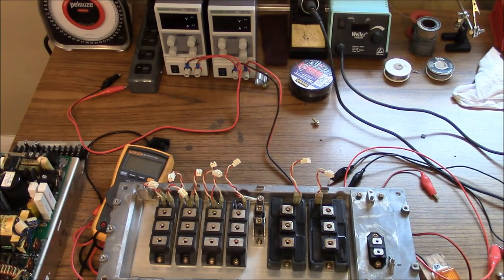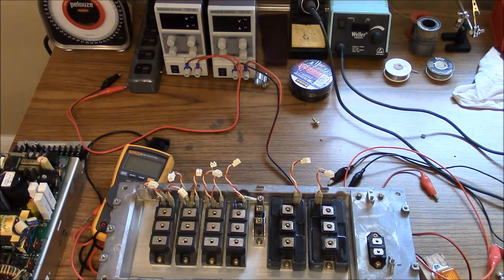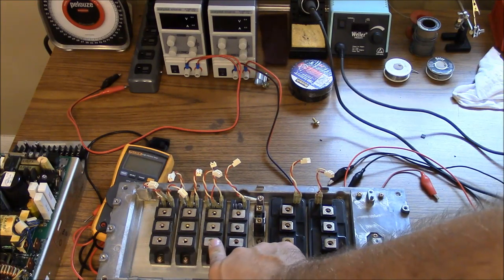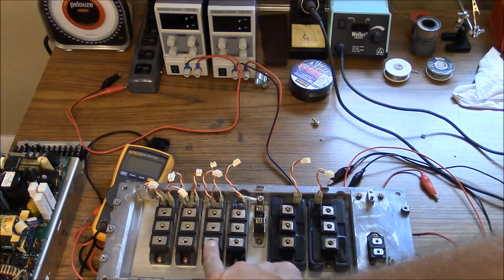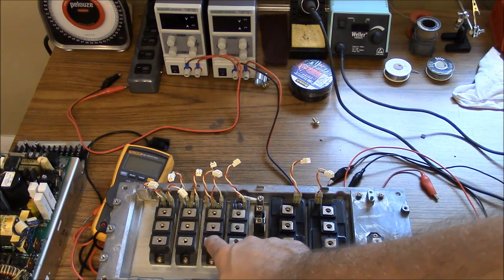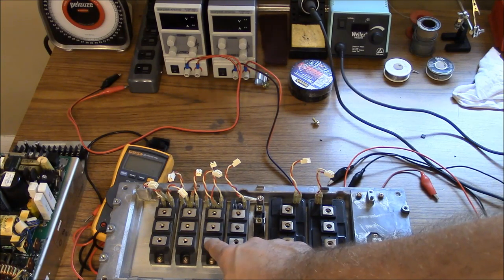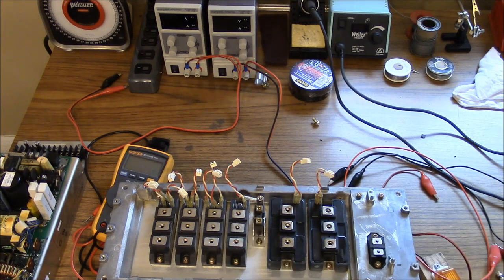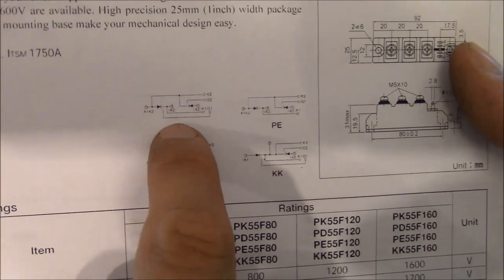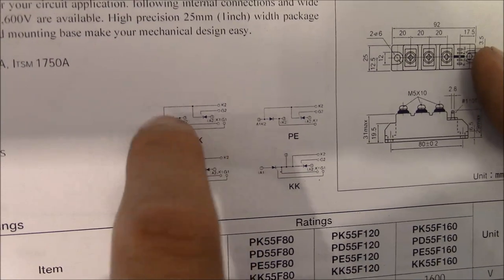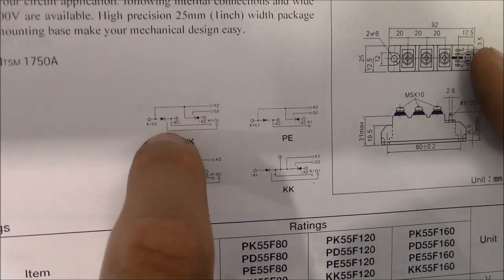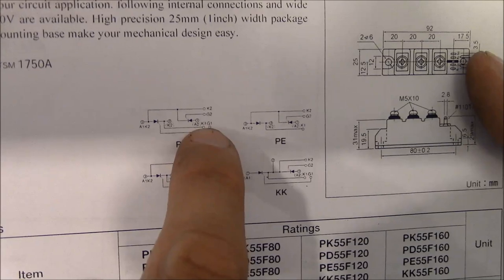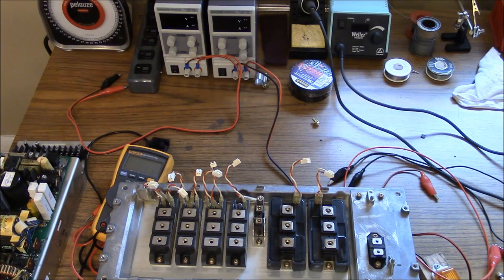Okay, so we're down to the high power side of the power supply, or the high voltage side I should say. So these three modules right here are the rectification. Each one of these is a full wave rectifier, but basically these are thyristors or SCRs, so they are rectifiers, but they don't actually work as rectifiers until they receive a gate voltage. And this is the datasheet right here. And hopefully you can see this - this is the schematic right here for the one that we have in our circuit. And so each side functions as a diode and does rectification, but it doesn't actually allow any voltage to cross until it gets some voltage at the gate.